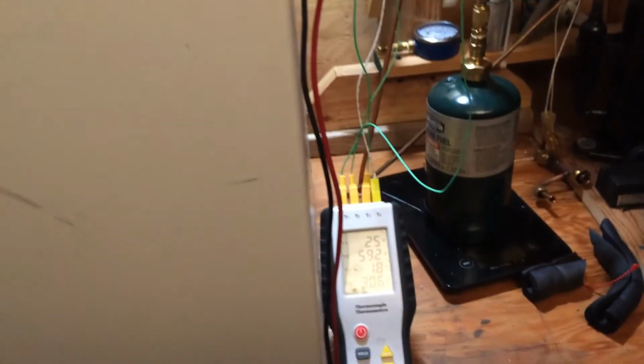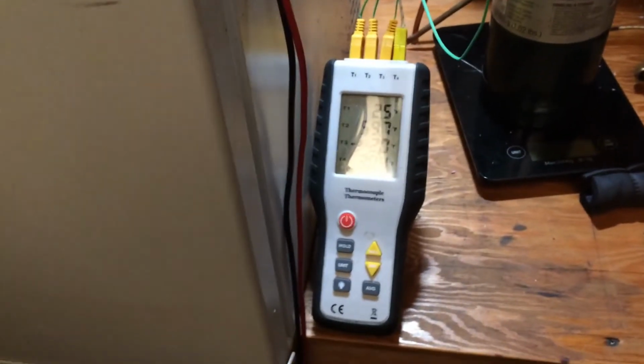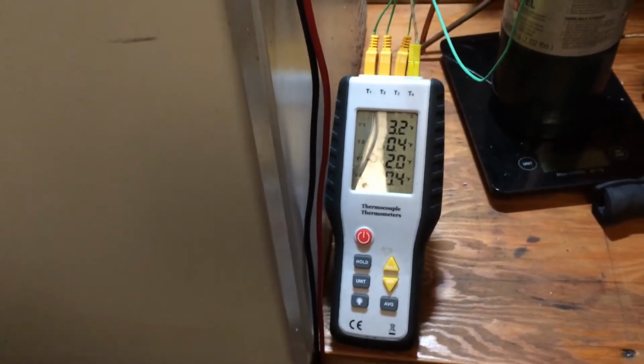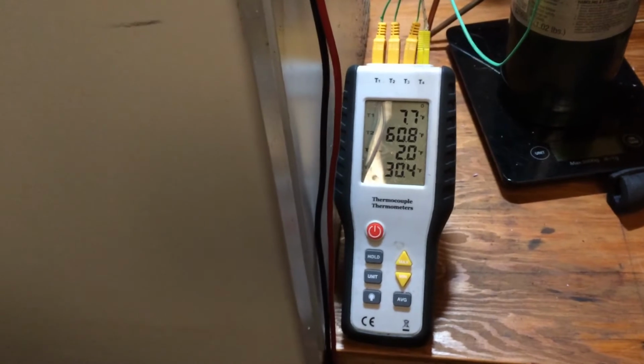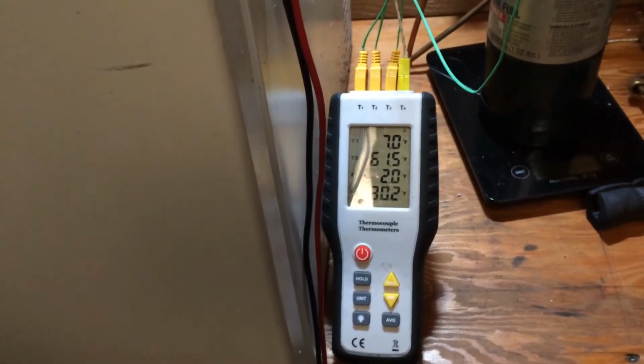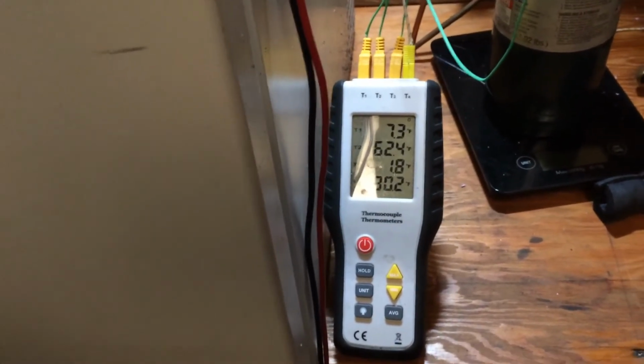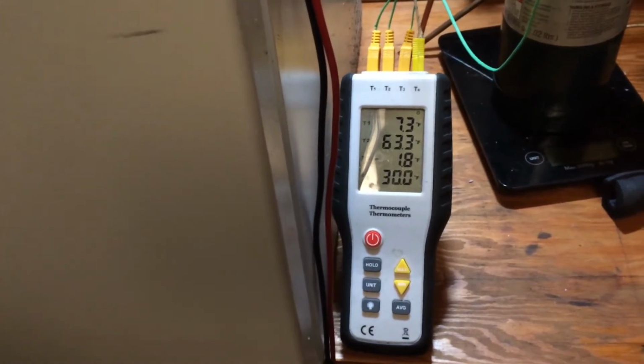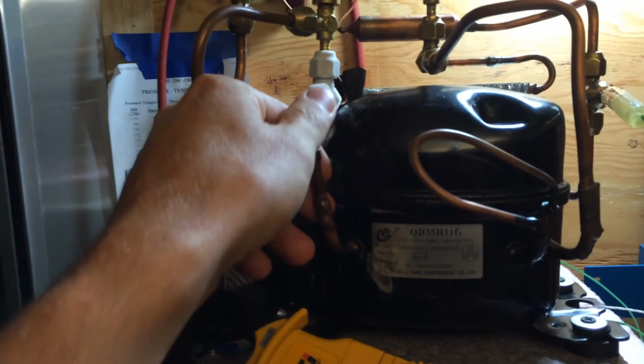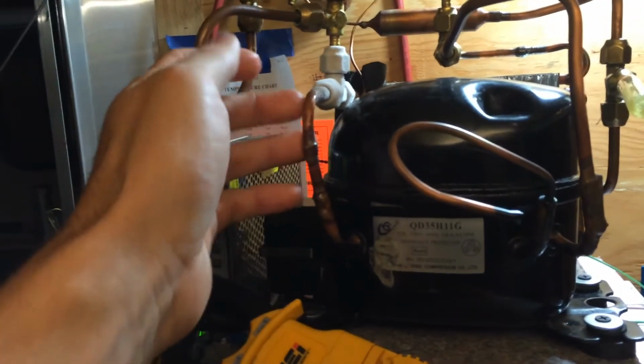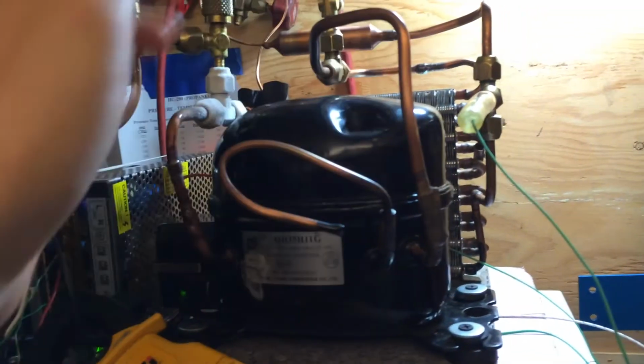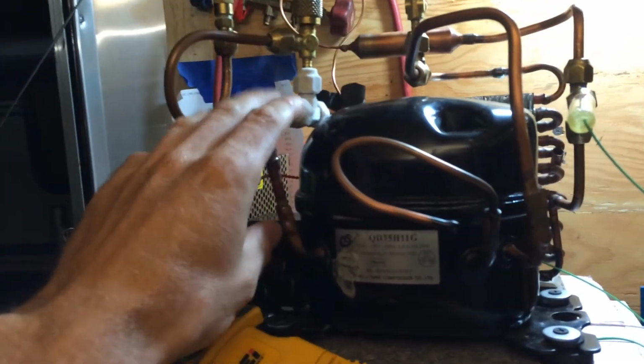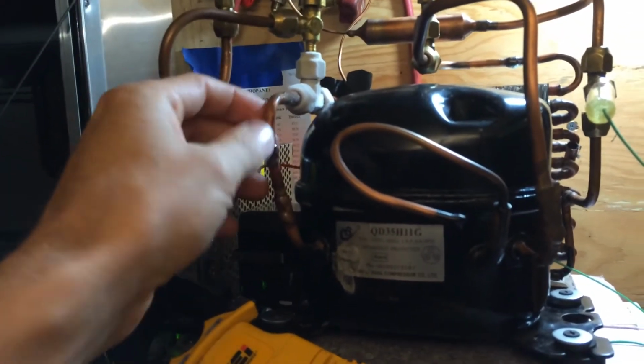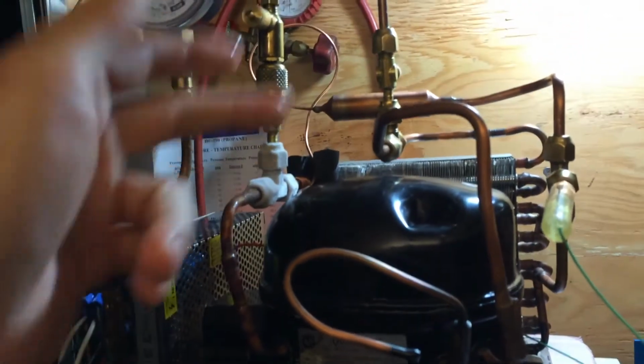About the charge - it's probably less than 2 ounces, I don't know exactly. I can charge it during startup when the whole thing is warm, but that doesn't tell me much, because once I get down to these low temperatures, mass flow changes and the amount of heat flux into the evaporator and out of the condenser changes. So the whole dynamics change, and a refrigerant charge appropriate at high temperature isn't necessarily appropriate at low temperature, since we have a fixed bore capillary tube.